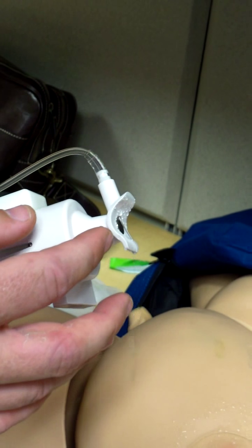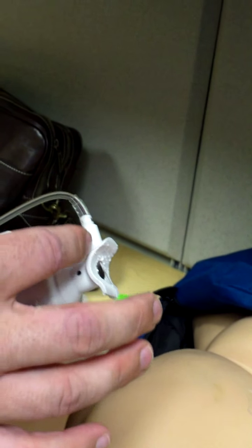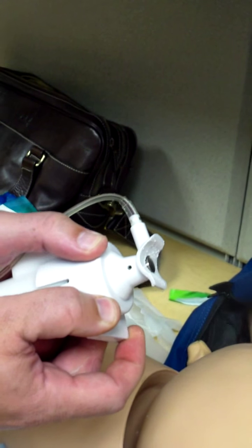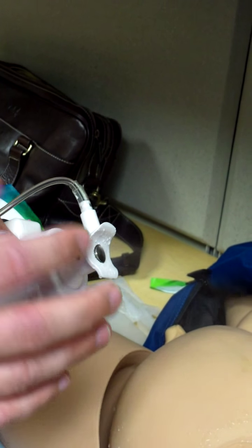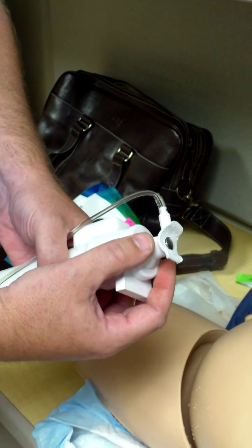Now, why is that happening? It's happening because the mist is not getting on the transducer tip. It's just falling out. So when you have it on full and you hear that snap, that's where it's misting. So you have to wait till it snaps. Push it in hard and snap it. Yep, push it in hard.